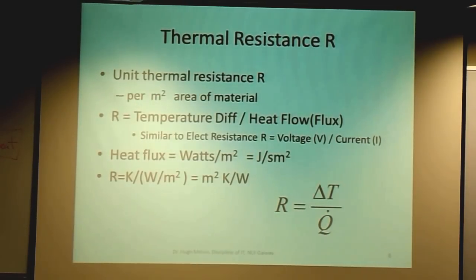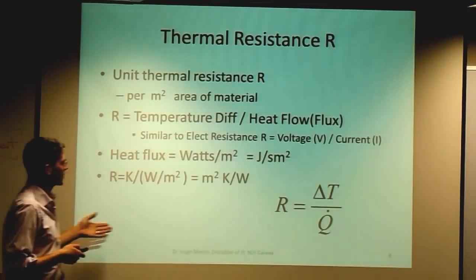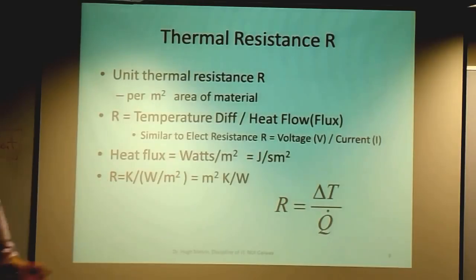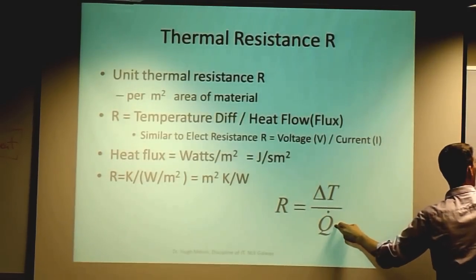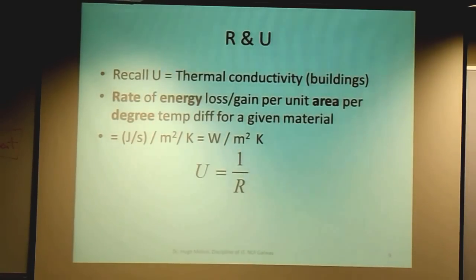Just to keep your eye on units, because I'm a stickler for units. It's defined per meter squared of material. If you were to define thermal resistance, you have your temperature potential, analogous to your voltage potential, and you have your heat flow, which is the same as current flow. The relationship between conductivity, or U-value, and resistance is an inverse relationship. U is one over R, R is one over U.